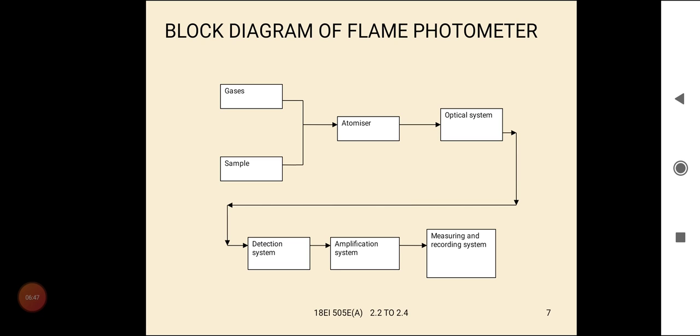The prism monochromator is used to produce a narrow beam of radiation energy with a selection of particular energy. That means when radiation is falling on the prism monochromator, different wavelengths of light are dispersed at different angles. So here the required wavelength can be selected by using prism monochromator, then passed on to the detector through the exit slit.